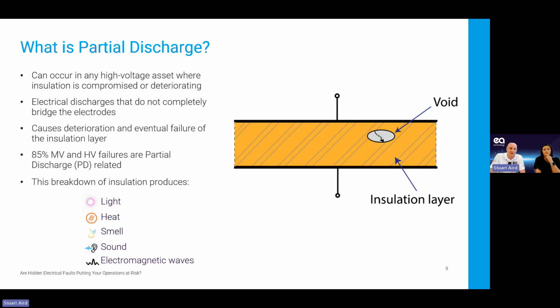What will happen is once you've got partial discharge, it will continue to deteriorate. So wherever it is within the insulating material, it will always start to continue to break down that insulation layer, and eventually will lead to failure. And different types of discharges will have different failure mechanisms and times. So PD is a key indicator. So 80 to 85% of medium voltage and HV failures are related to partial discharge activity. That's what we've seen looking at failure investigations. And we've got a forensics department here in EA, and we can look through why these things fail, and also things like the DINSOPs and NEDS database back up that kind of information as well.